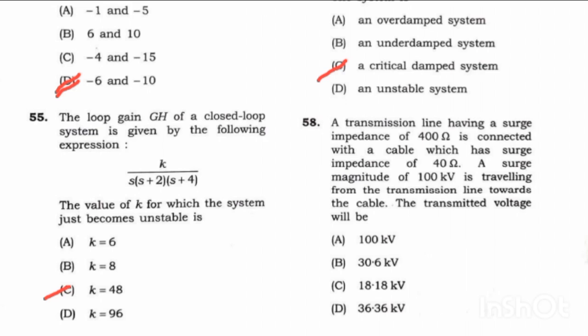Question 58: A transmission line having a surge impedance of 400 ohm is connected with a cable which has a surge impedance of 40 ohm. A surge magnitude of 100 kilovolt is traveling from the transmission line towards the cable. The transmitted voltage will be: A) 100 kilovolt, B) 30.6 kilovolt, C) 18.18 kilovolt, or D) 36.36 kilovolt. The correct answer is C.